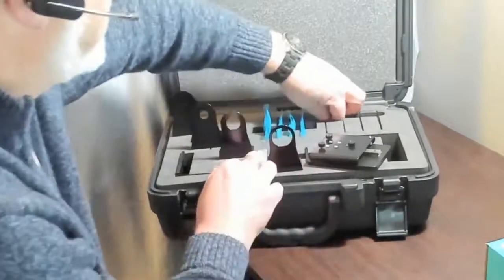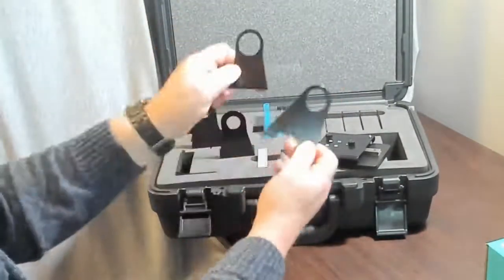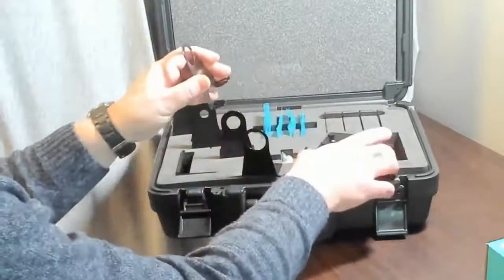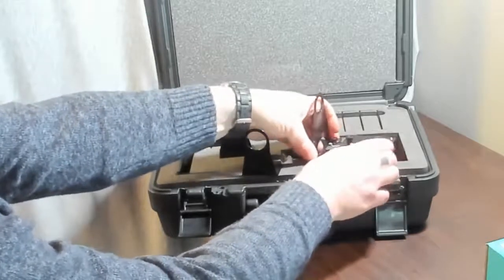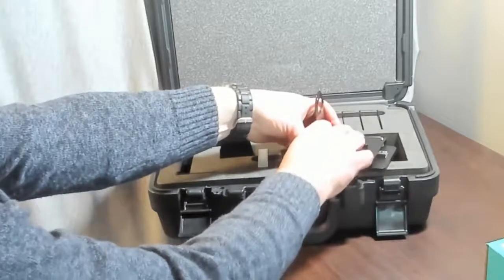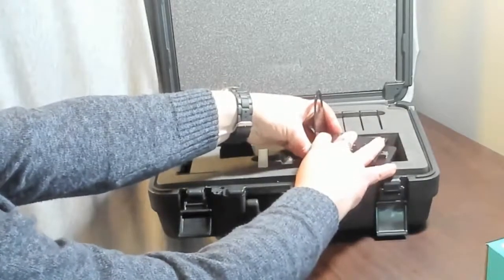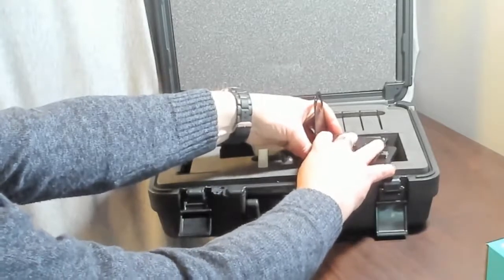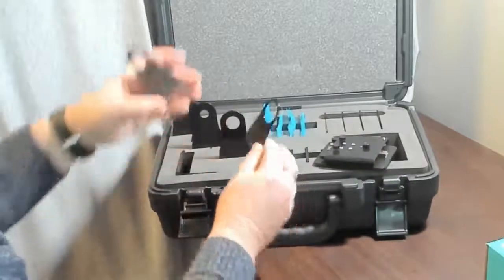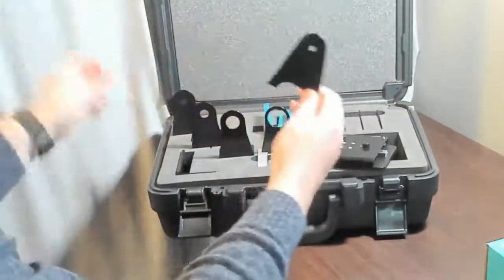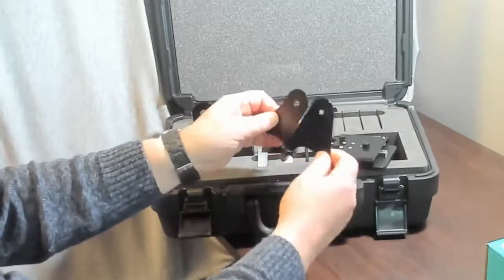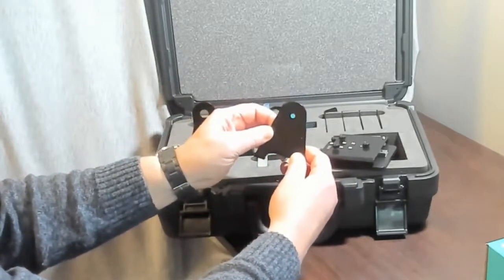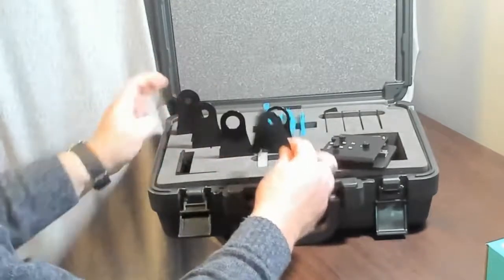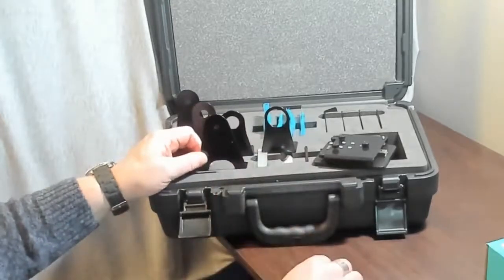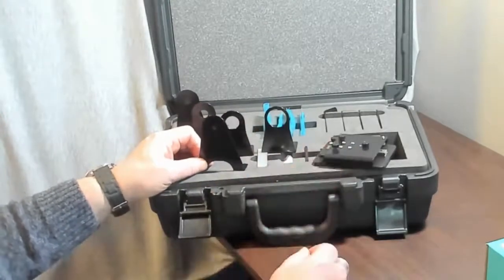So there's 2 for each, because what will happen is one of them, these are both the 25 millimeter, for example, one piece is going to connect down here and sit against the sphere. The other piece is going to connect here, and then the spring load will cause these 2 to behave like a clamp and hold the sample in place, with the opening just the right size for me to do my 25 millimeter aperture. And of course, we've got the other sizes, both pieces. So if I was going to do the other extreme from 25 mil, and I was going to be doing 6 millimeter, I'd have this piece and this piece coming together to hold the sample in place to do the measurement of a very small area. So those are the components inside of this kit. So let's move on and take some of these and put them together and actually do some measurements.